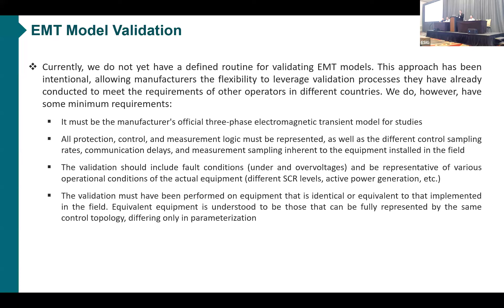The validation should include fault conditions, under and over voltages, and be representative of various operational conditions. So we want tests at different SCR levels with different active power generation, etc. And the validation must have been performed on equipment that is identical or equivalent to that implemented in the field, because some manufacturers have several models of inverters, for example, integrated in our system.